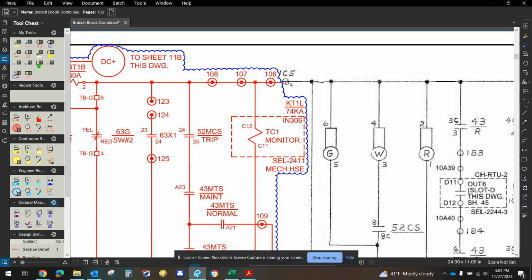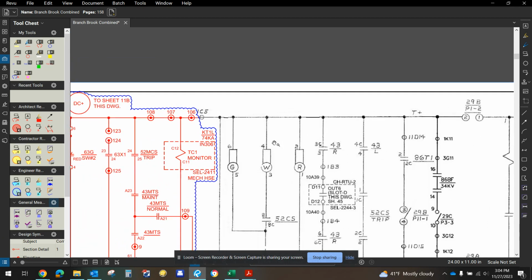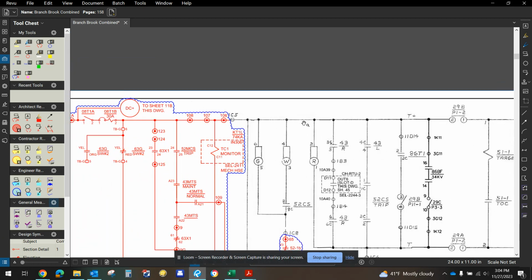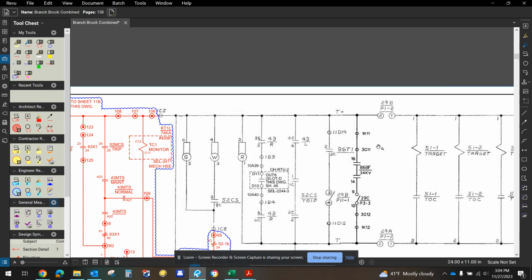I use a rule of 2. In panel 1, terminal block Charlie 5, my new circuit terminates on one side, and on the other side of the terminal block is my existing circuit, which I did not disturb. So I'm going to pick 2 points within the existing circuit and prove to those points. Maybe here, maybe here. That is verifying that I did not disturb the actual trip rail, positive rail, and did not remove any of these wires by accident.